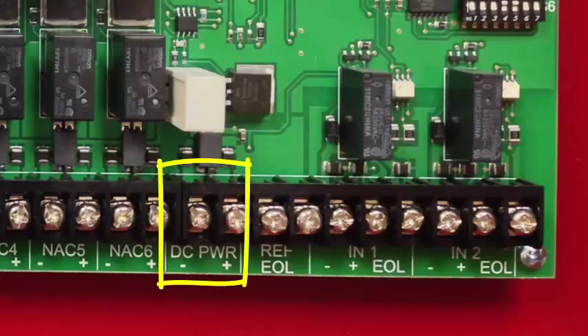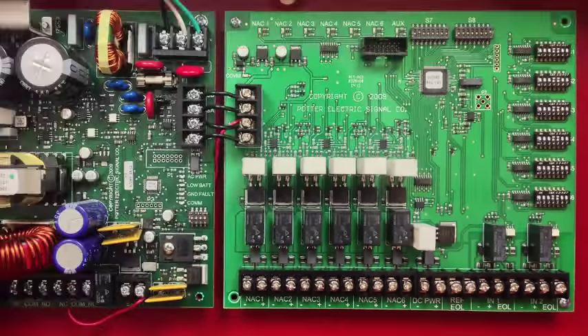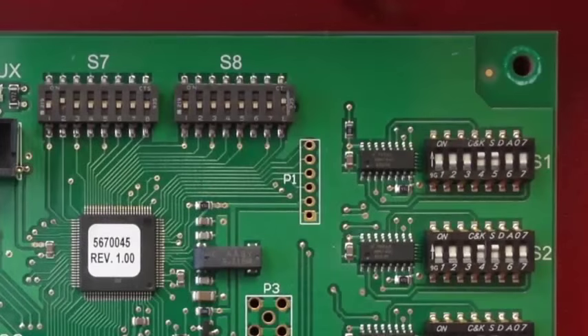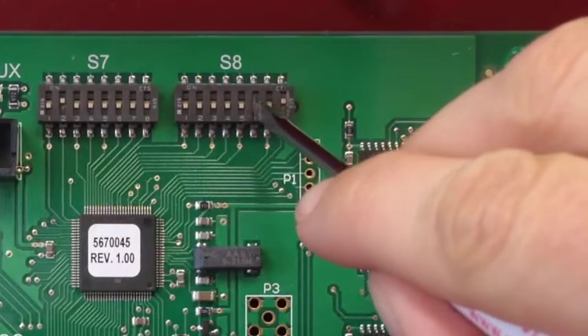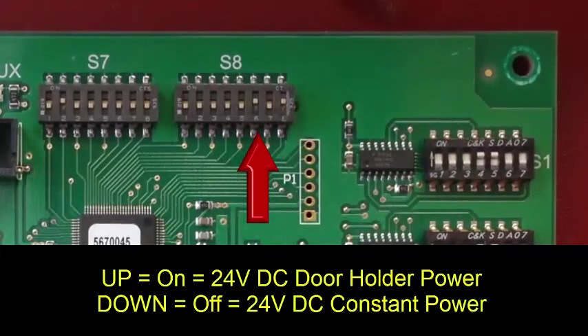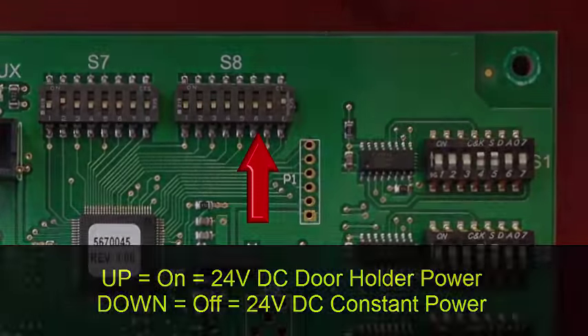The next set of terminals is the DC power aux power terminals. You have 3 amps of power that can be configured as continuous or door holder power. The DC power terminals are programmed through switch 8 found at the top of the board. On switch 8, set DIP switch 6 to the ON position for 24V door holder power or leave it in the OFF position for 24V constant power.